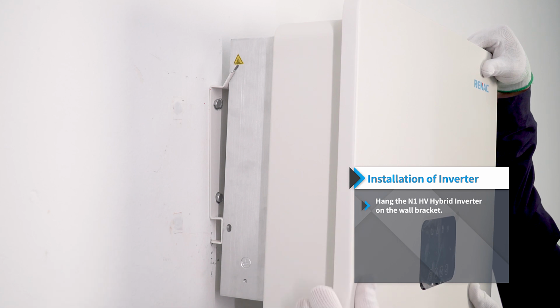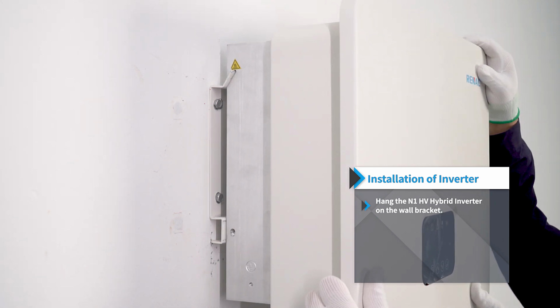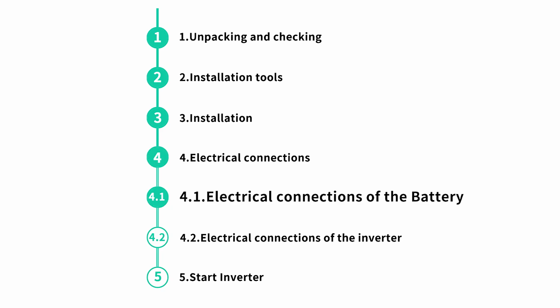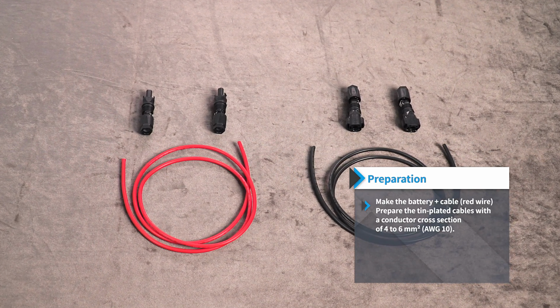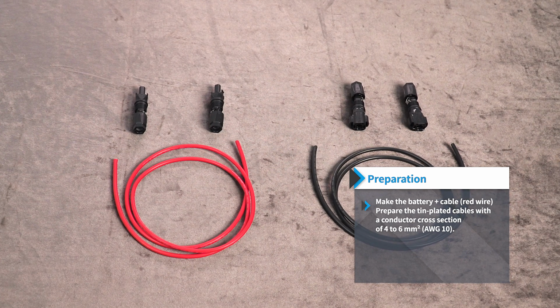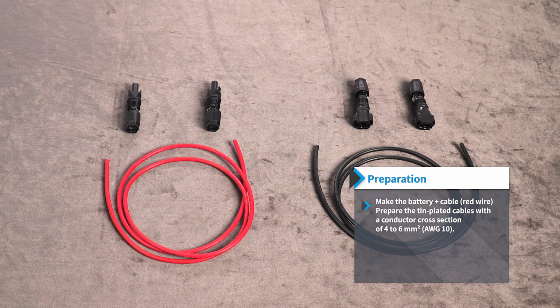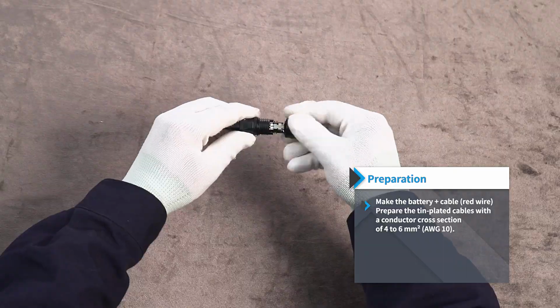Hang the N1 HV Hybrid Inverter on the wall bracket. Fix the screw. Electrical connections. Make the battery positive cable, red wire. Prepare the tin-plated cables with a conductor cross section of 4 to 6 square millimeters, AWG10.